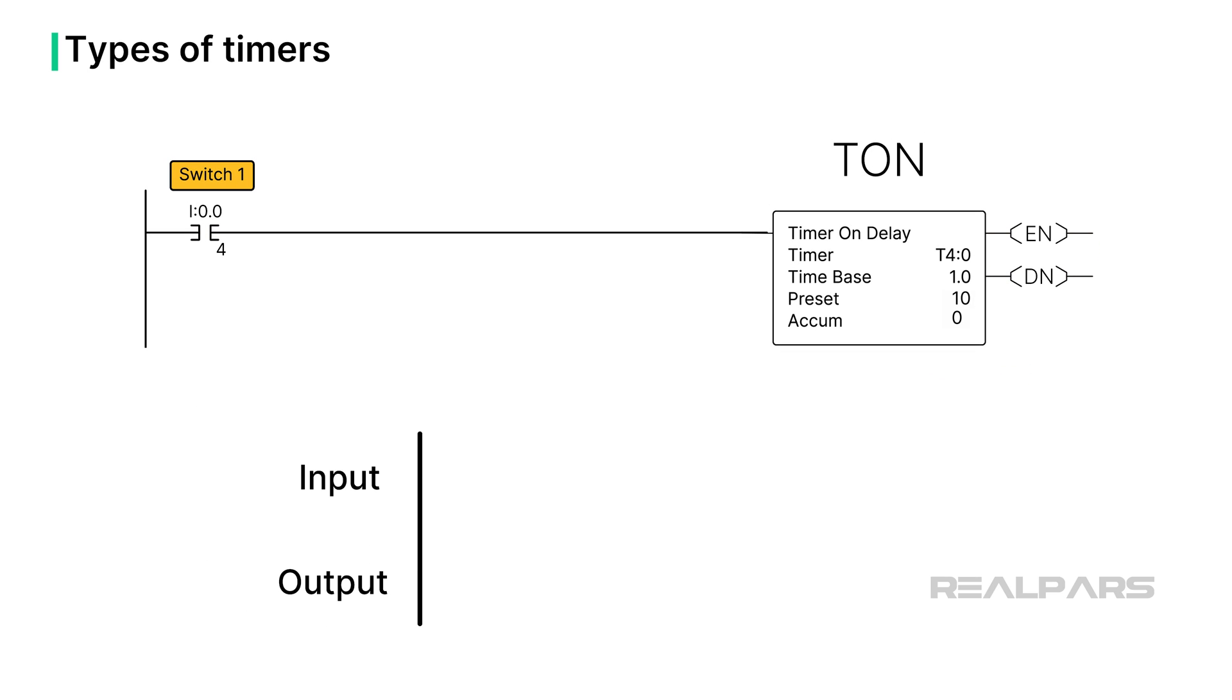The timer just illustrated is called an on-delay timer. When the logic upstream of the timer on the same rung is true, the timer is enabled. The timer times until the preset is reached and the done bit is set. If the timer input is no longer enabled, the timer resets. Once set, the done bit stays true until the rung goes false.